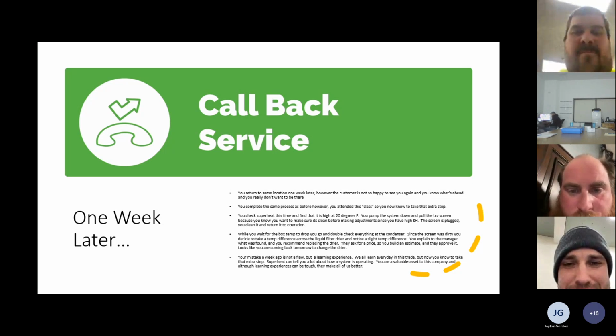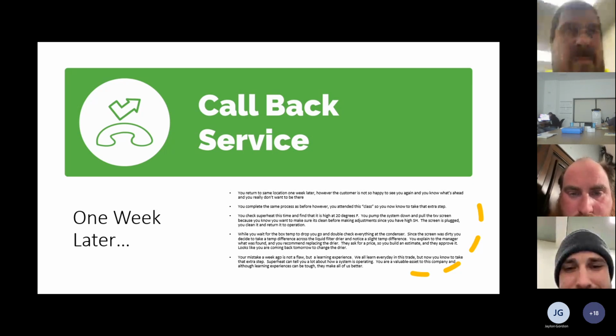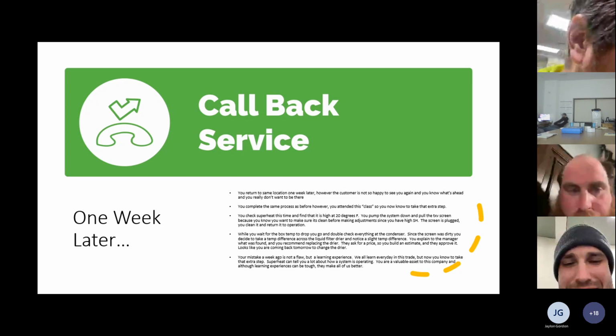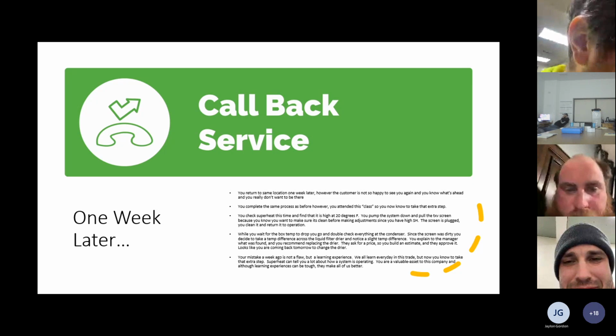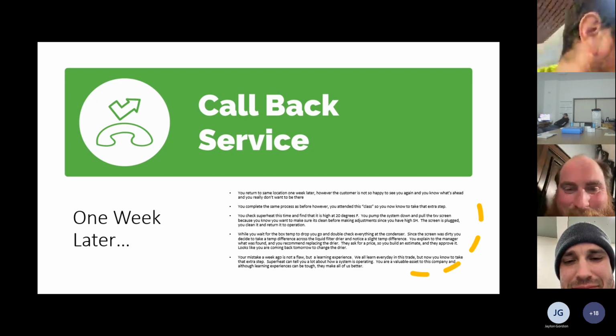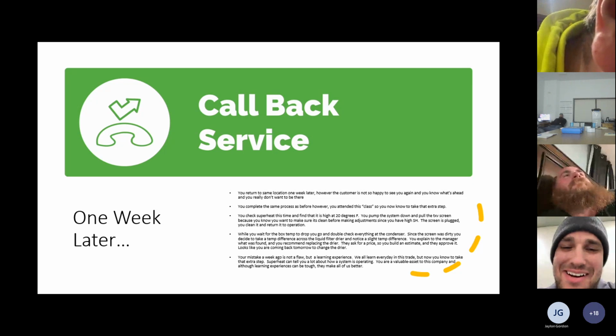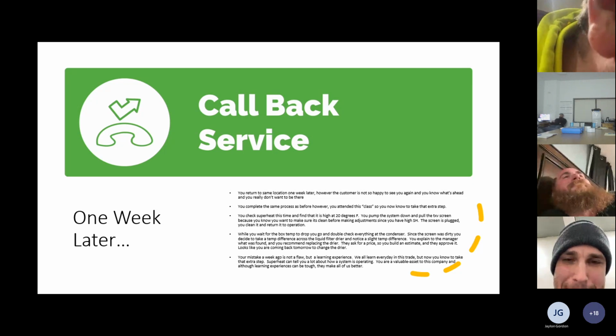Well, you did clean the condenser because it was dirty, remember? It had high head pressure. So now, 1 week later, but Brad, to your point, yeah, I'm asking you why you didn't drop that pan and clean the evaporator coil on the inside. So correct, thank you. What I should have put in there was, per Travis, I also dropped the pan, cleaned the drains, everything.